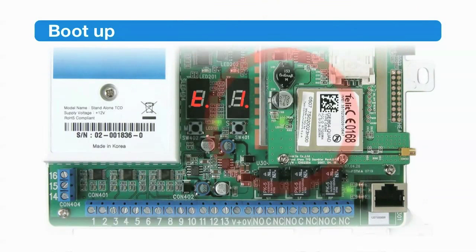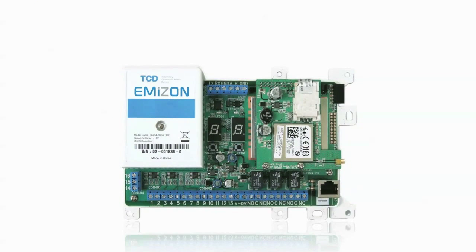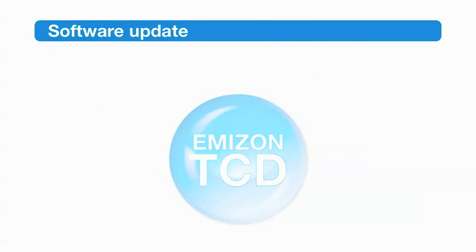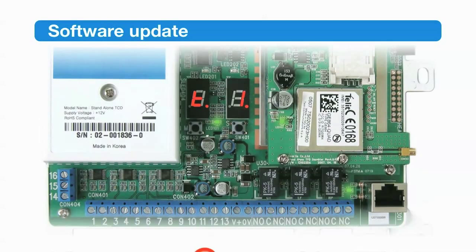Note: the interval between flashes on the GPRS LED slows down from once a second to once every 3 seconds once it's registered with the GPRS network. A key feature of the TCD is the facility to download the latest version of software. With the display showing TI, press the mode and set buttons together and hold until UF is displayed. Release and then wait until UC is displayed, indicating that the update is complete. If RR instead of UC is displayed, repower the TCD and repeat the boot up and software update process until UC is shown.